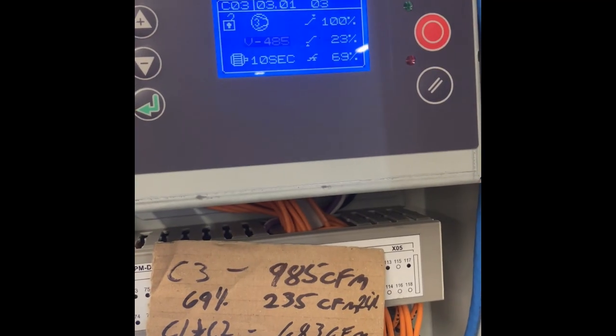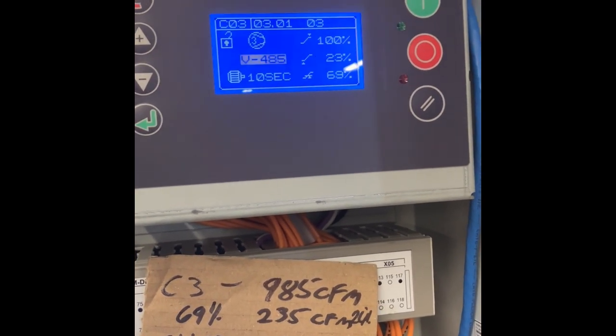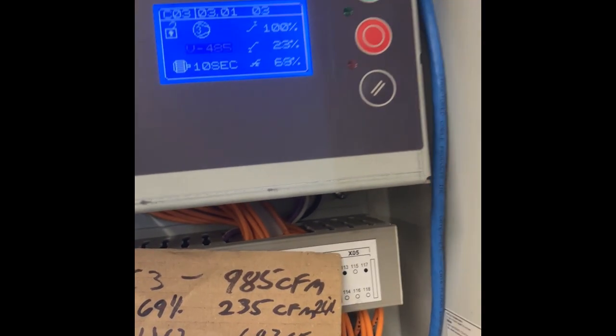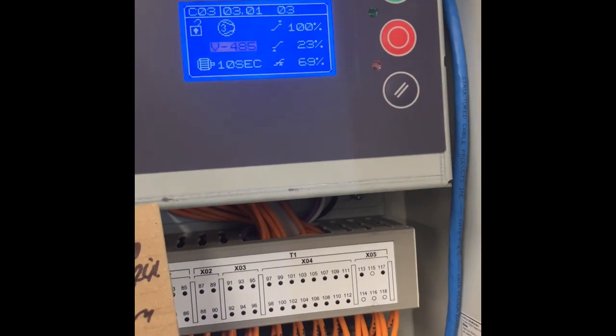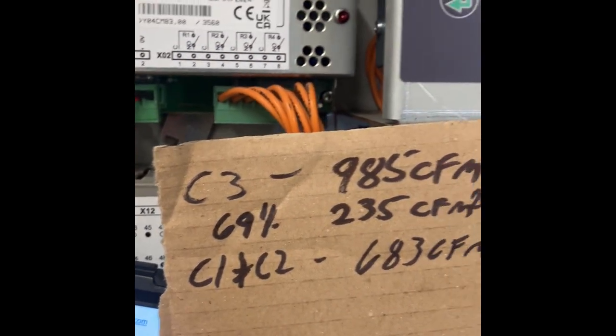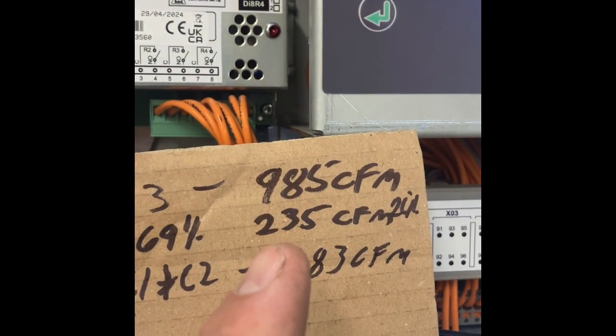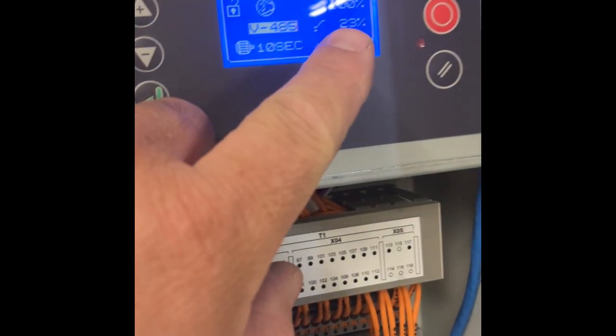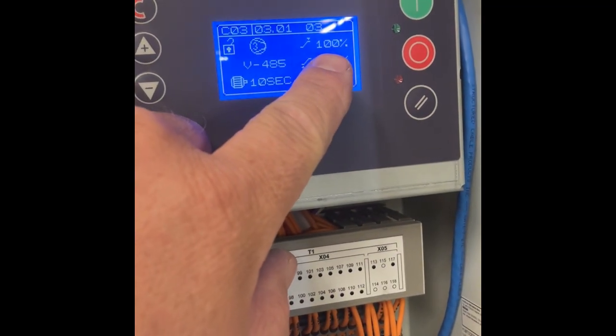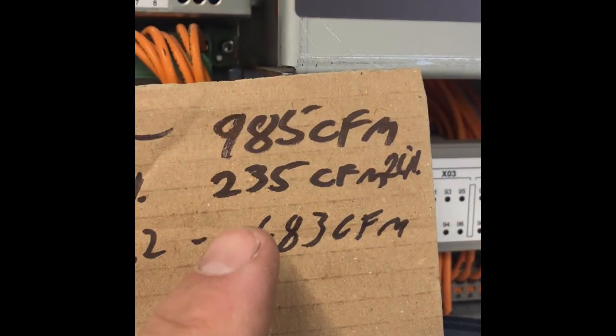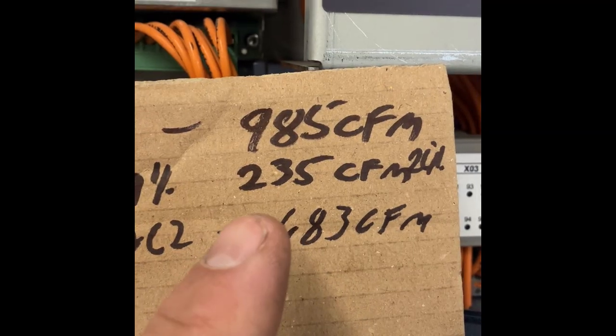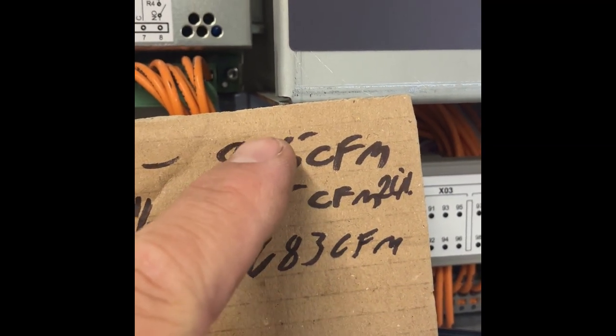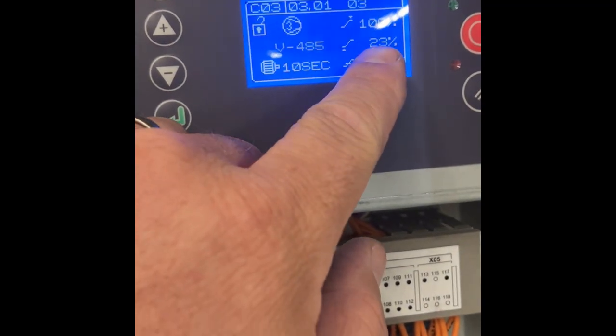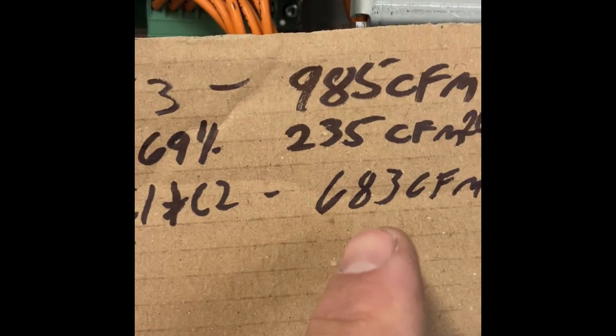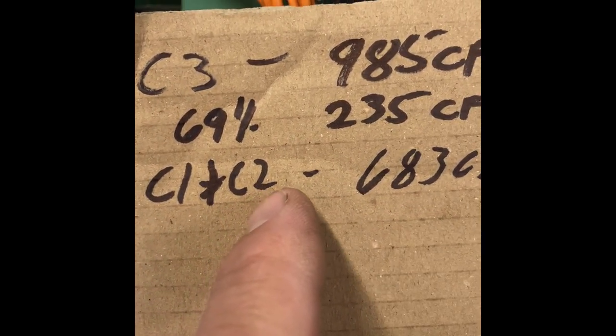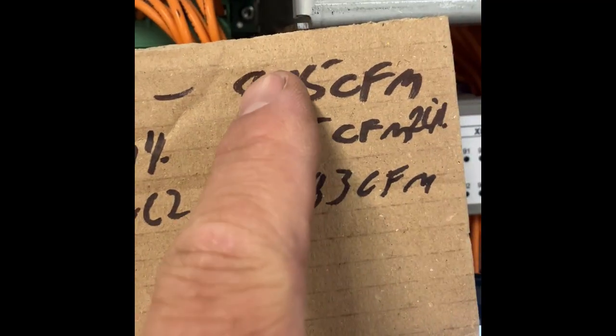This gets a lot of people screwed up. I've seen this set up wrongly a number of times. So what you got to do is you have to figure out what your largest compressor is. So in my case, it's C3. At full load, puts out 985 CFM. Okay, so C3 at its peak output is 100%, and then my lowest output, 235, when it's at minimum speed, is 23% of that. So my lowest output, 23%. Now, the 683 CFM that C1 and C2 are capable of putting out is 69% of my largest compressor.